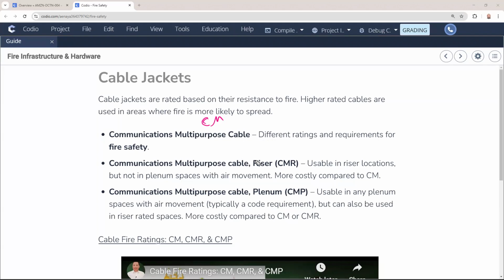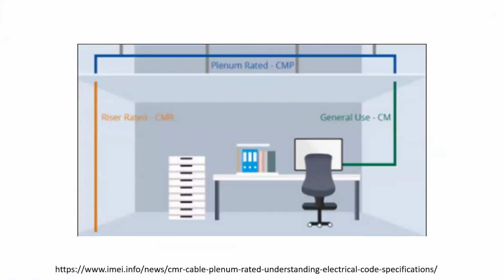The other type is CMR. R stands for riser. Riser is the space that goes between floors. These ones are better. So this one is bad. This one is better because it can resist the fire to a certain extent, but it is more expensive. On the other side, CMP is the best when it comes to resisting the fire, but it is more and more expensive. So it is both better and more expensive. This one is cheaper, but bad when it comes to resisting fire. So somehow this is the visualization.